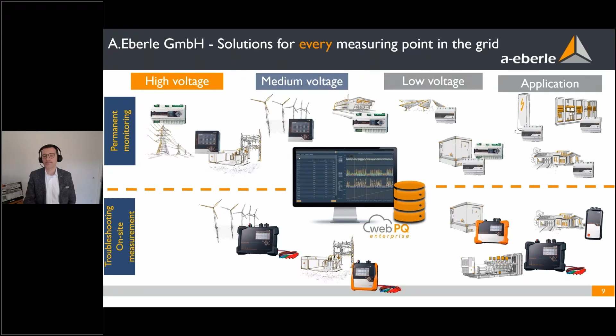But still there is one issue. For me it is absolutely clear: if you have an issue in the grid where you have to measure it, you always have to do that with a mobile device. The combination of both is the main aim we can handle with our new software, which we provide this year, called WebPQ Enterprise. It will be possible in the future to bring data directly from here into the software. This is a strategic decision we made internally, because we know the issues in the grid exactly and how to handle them. It is always a combination of permanent monitoring systems combined with on-site measurements in case of troubleshooting.